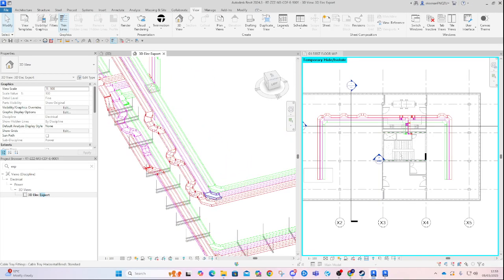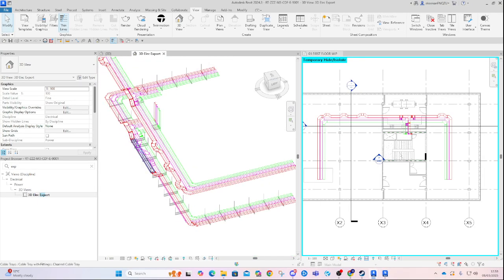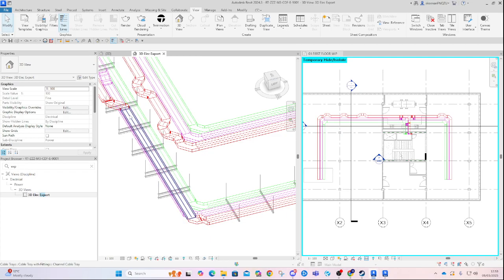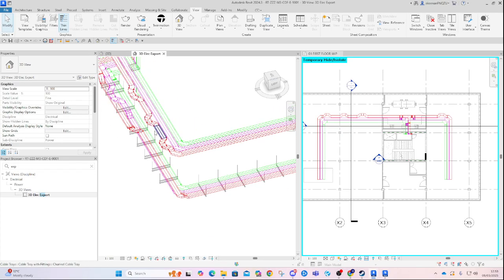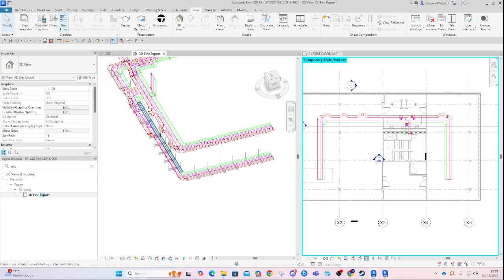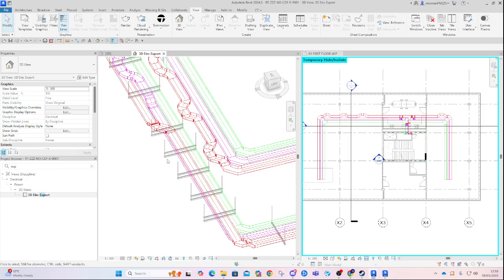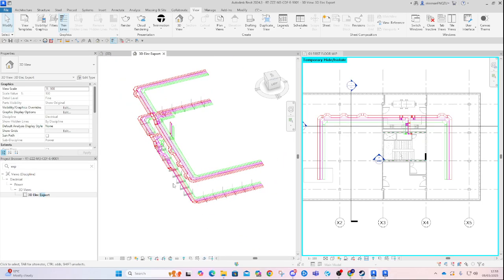I snake around the things we were clashing with around here. This was an exercise just to show how cost saving it actually is to do what I've done on the ground floor against what it is here on the first floor. It's an interesting cost saving exercise to show whether extra additional bends like this are more efficient, or whether it is more efficient to do fewer bends and add an extra tier in the brackets.